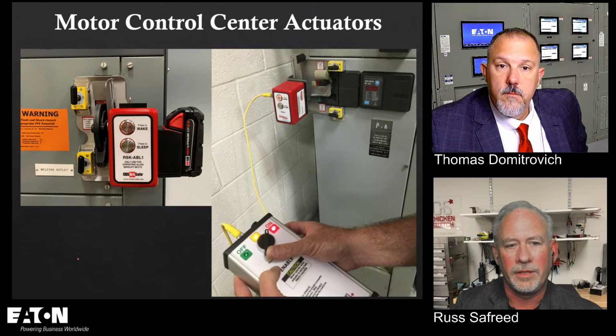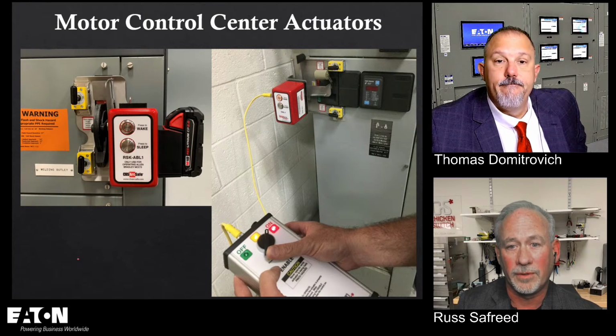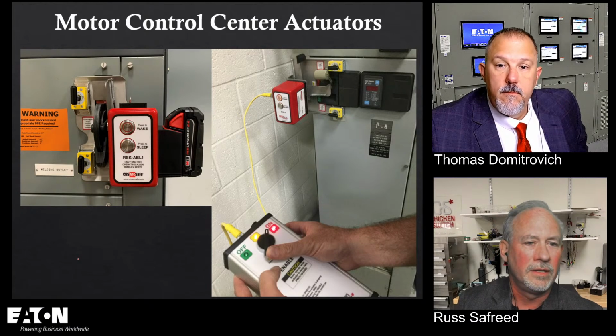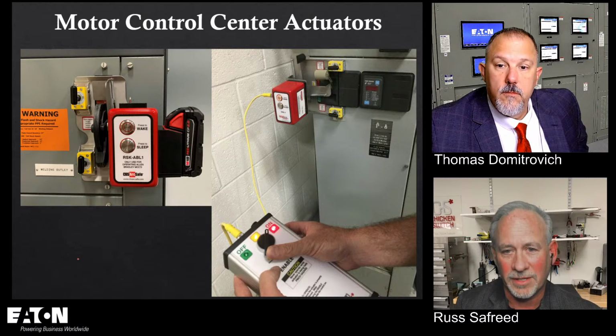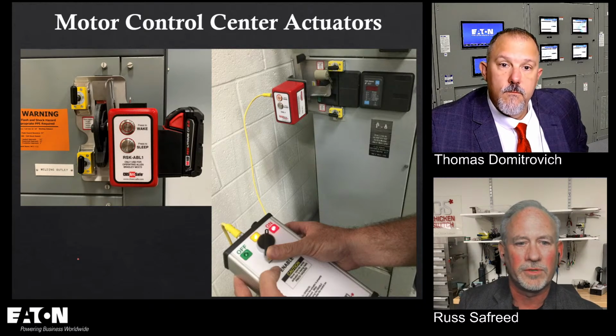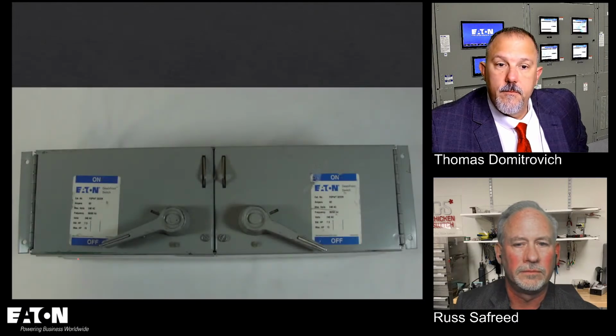But typically you find you operate MCCs a lot more than your substation breakers, so the risk goes up because the amount of exposure goes up. Yeah, typically a lot more switching with motor control centers. Absolutely.